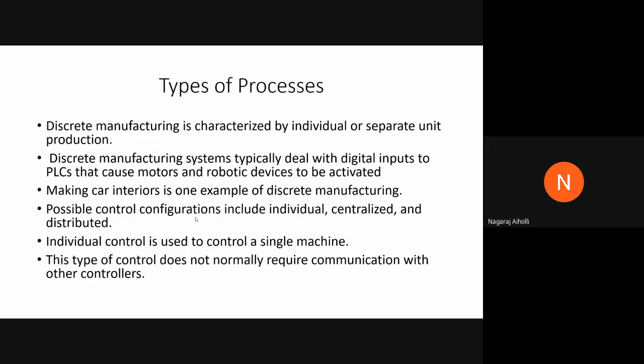In the individual control configuration, there is a single machine which is controlled, and this type of control does not require communication or exchange of information between two PLCs. Fine. Then next one is, students, the centralized control system, in which one PLC controls the other PLCs. There is exchange of information between the central computer or the central PLC and the other PLCs. The main feature of centralized control can be summarized like this: each individual step in the manufacturing process is handled by a central controller. If the main controller fails, then the whole process will stop. So this is the disadvantage of the centralized control system.